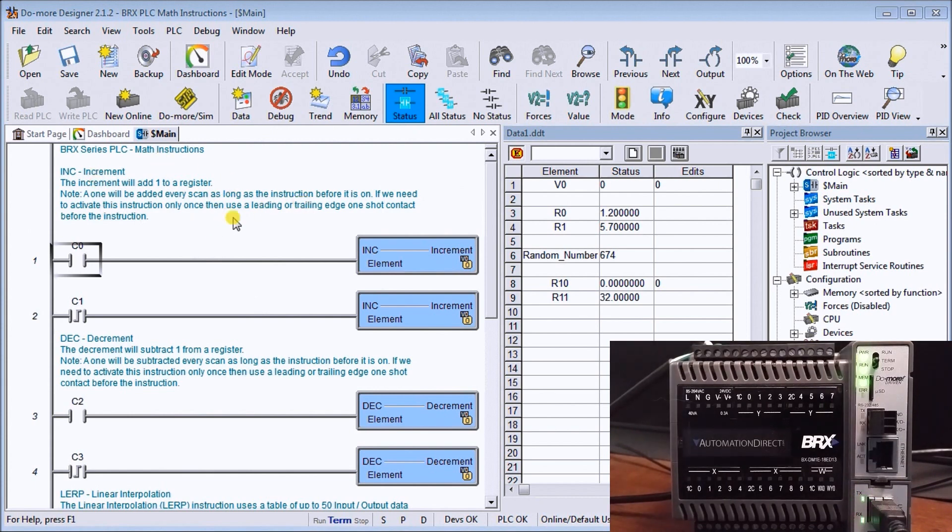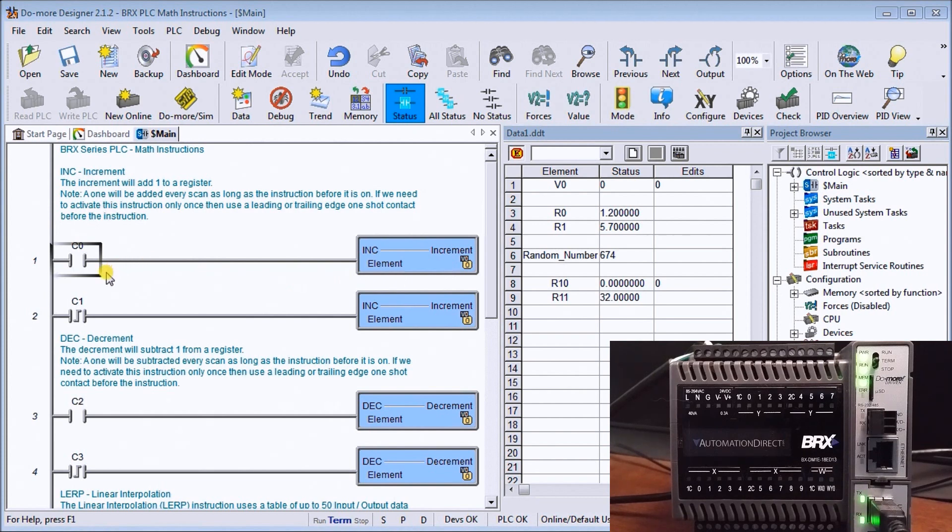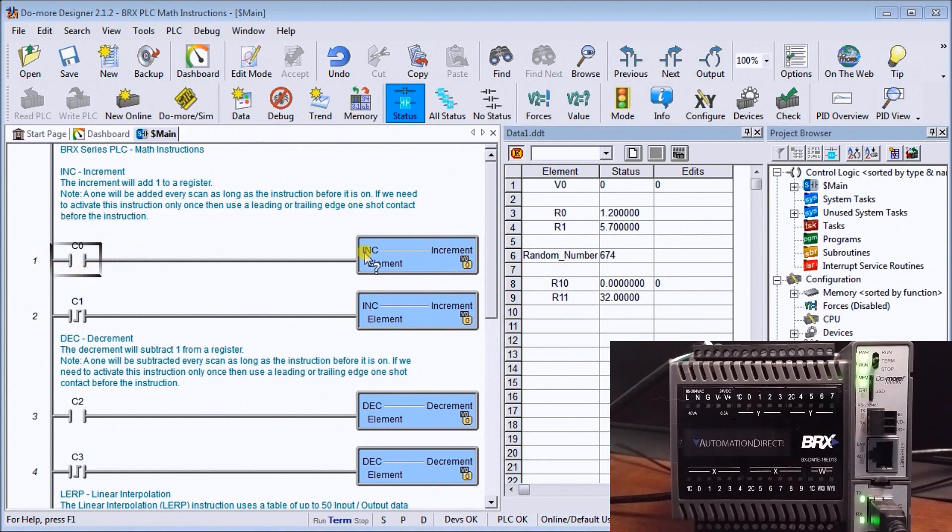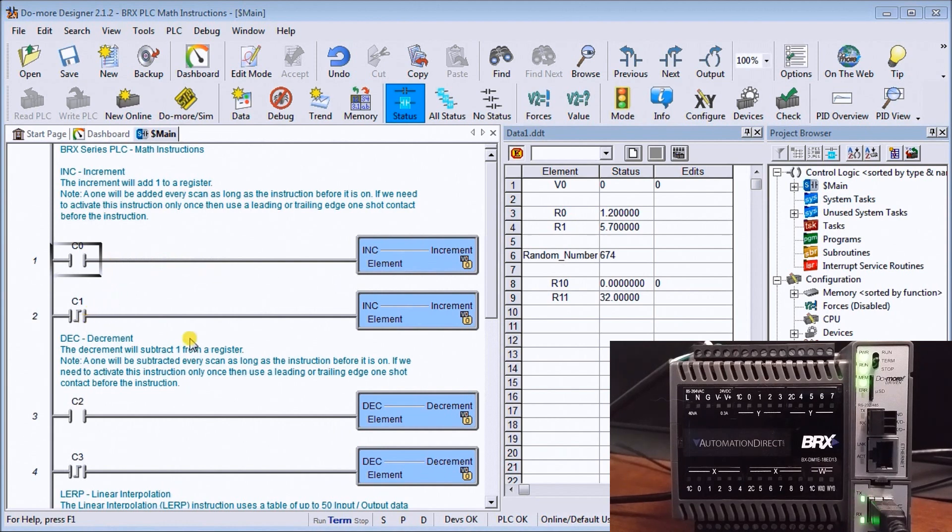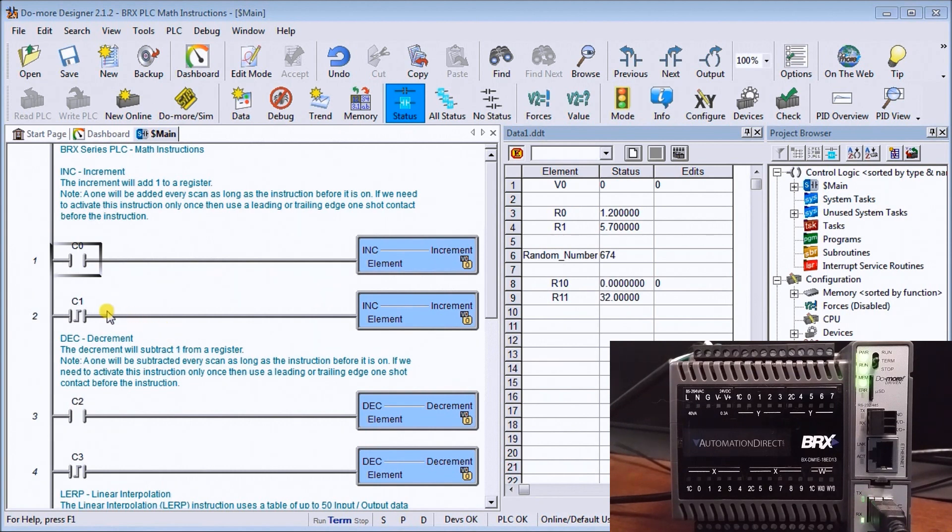If we look at our increment instruction, I have two different ones incrementing to the same address v0. In the first case, I'm using the continuous on instruction, so when it's on it's going to increment that v0 by one every scan as long as c0 is on. The next one is on c1, which activates once there's a transition from off to on, or the leading edge one shot, so it should increment only once.